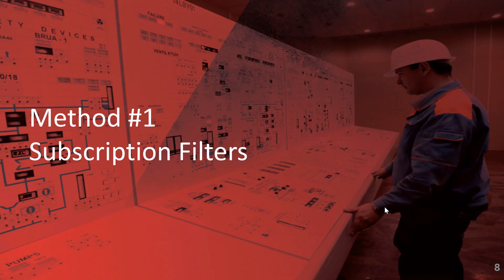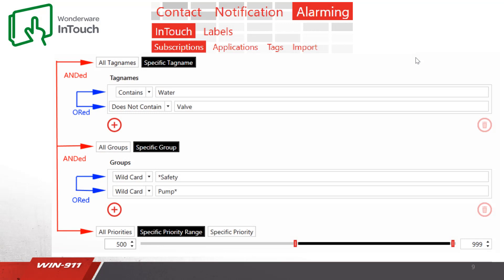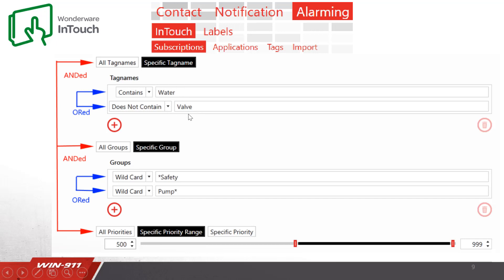First, I'll be demoing the subscription filter method. Inside of WIN911, on the Alarming InTouch Subscriptions tab, you'll see your configuration. You can filter on specific tag names, specific group, and a specific priority range. These items are all ANDed together and you can use any combination. The blue items individually are ORed. In this example, we're filtering on a tag name that contains 'water' but does not contain 'Valve', and a group of wildcard 'safety' or wildcard 'pump'. The asterisk is the wildcard.